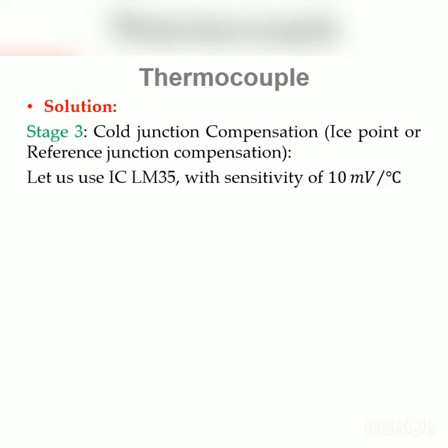Now stage 3 will be the cold junction compensation, which is also called ice point or reference junction compensation. Already we have discussed why there is a need for cold junction compensation, because whatever the temperature difference between the room temperature and 0 degrees Celsius, that temperature difference and the corresponding millivolts must be added to the millivolts processed and given by the thermocouple.